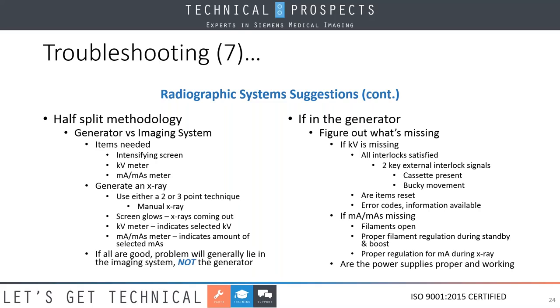Are you getting proper regulation during standby? In other words, are our filaments staying warm? Is the circuit operating correctly? Are we boosting to the appropriate level to create the space charge cloud? During X-ray, are we backfilling it to keep the X-rays going and getting a proper amount of mA coming out? All this is tied to power supplies and whether they are working correctly. So these are things we need to look for on the generator if we're having issues.